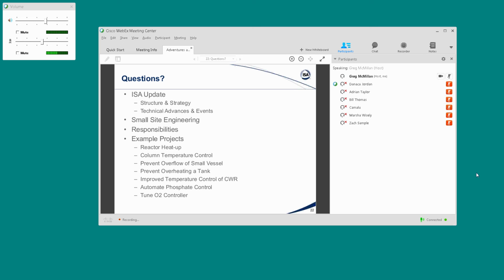So now that primary loop output has to have output limits, 25 degrees as low limit and 75 degrees as high limit, and in most cases the anti-reset windup limits should also be set equal to those output limits. So low anti-reset windup limit 25 degrees centigrade, and the high anti-reset windup limit equals 75 degrees centigrade. So yeah, that's a common problem, and there are some other problems, I guess, as you migrate from one system to another.